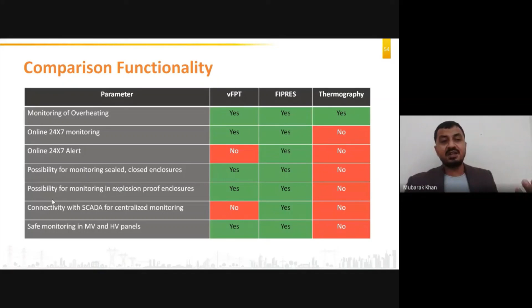Now comparison, and there is one more method with which people are doing thermography, that they are using the IR windows. Just remember, IR window can make visibility of only the joint which is directly accessible from that IR window, not the whole panel. There are so many joints, bends and turns inside the panel, and your camera cannot reach everywhere. Camera cannot reach the jaw connections. Camera cannot reach other busbar, bend, busbar chamber, etc.